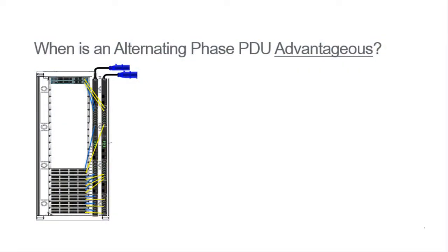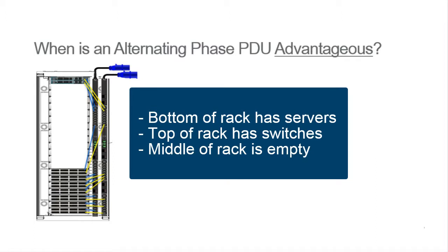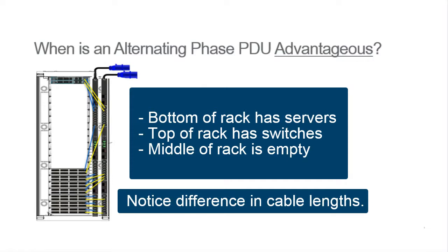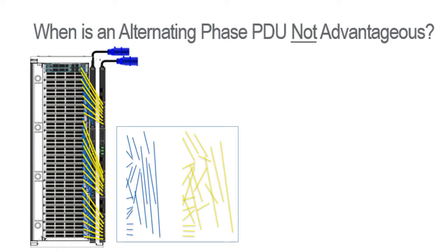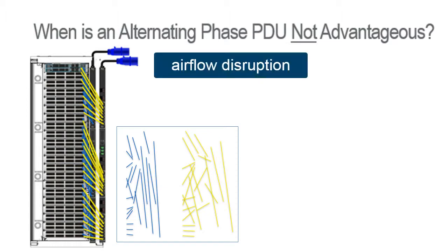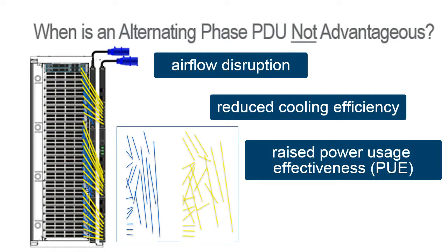So when is an alternating-phase PDU right for you? When the initial deployment is not a fully populated rack. For example, the rack shown here was initially deployed with the bottom third populated with servers. The switches are at the top of the rack, and the middle of the rack is empty. When using a conventional PDU, the initial cabling requires two to three different lengths of cable to achieve a balanced load. Over time, as more equipment is added, the cabling can become very messy, with lots of cable crisscrossing and different cord lengths in use, because each device added has to be connected to the phase that is out of balance. An installation like this can cause airflow disruption, reducing cooling efficiency, and raising power usage effectiveness, or PUE.